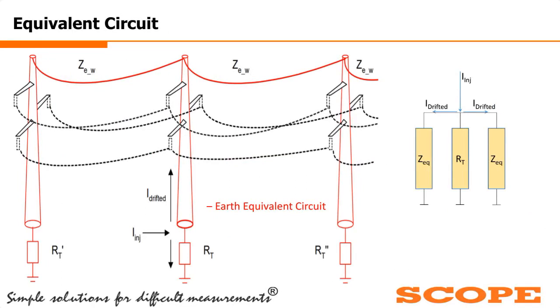Okay, so with the help of this type of tower footing resistance measurement instrument, we can easily measure the impedance. We can also measure the tower footing resistance as well as the tower footing impedance. Impedance will include the influence of adjacent towers, meaning the inductance and capacitance values can also be measured, and generally the resistance value is calculated with the help of some internal calculations.